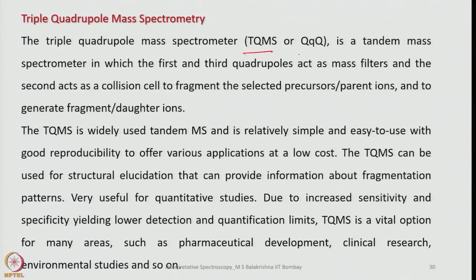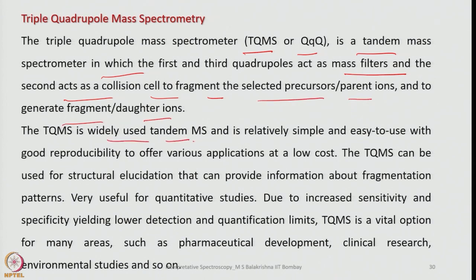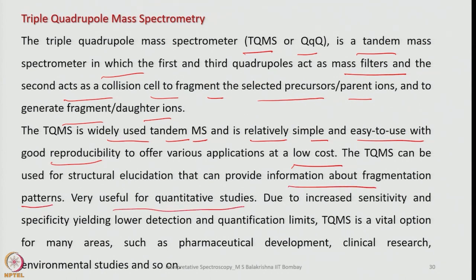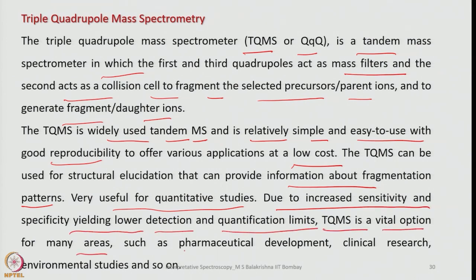Another instrument is triple quadrupole mass spectrometry, abbreviated as TQMS or QqQ. It is a tandem mass spectrometer in which the first and third quadrupoles act as mass filters and the second acts as a collision cell to fragment selected precursor or parent ions and generate fragment or daughter ions. TQMS is widely used, relatively simple and easy to use, with good reproducibility at very low cost. It can be used for structural elucidation and fragmentation pattern analysis, as well as quantitative studies, with lower detection and quantification limits — vital for pharmaceutical development, clinical research, and environmental studies.